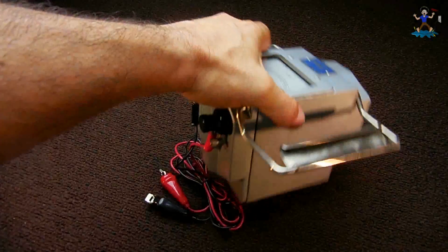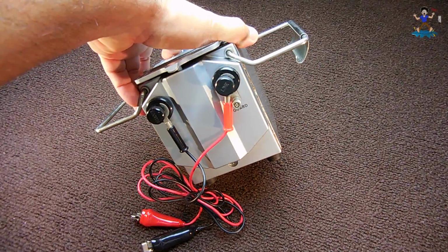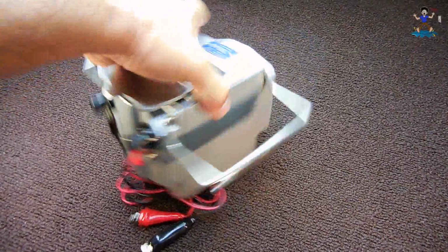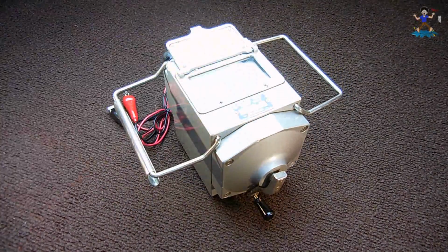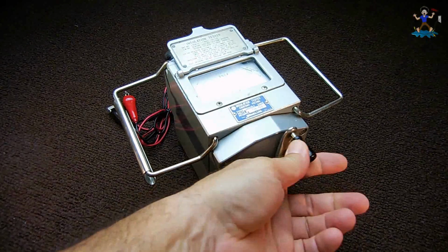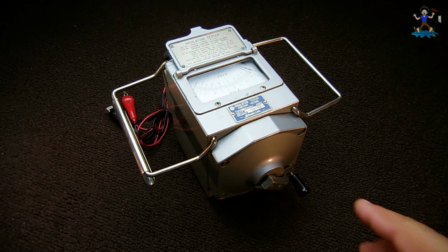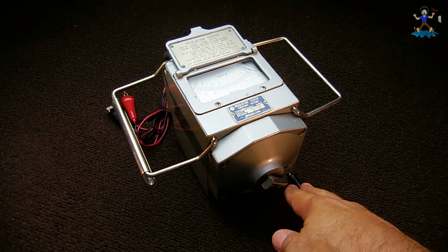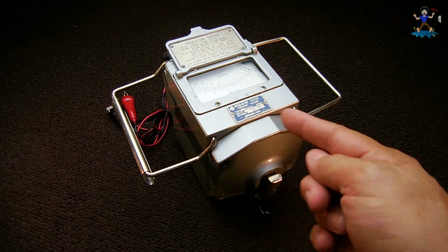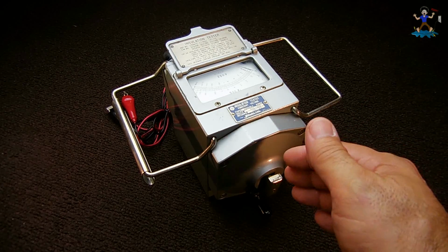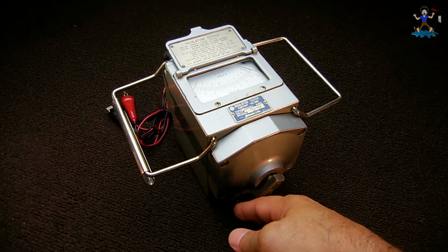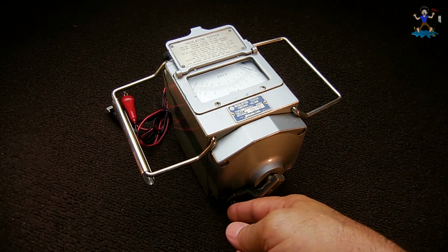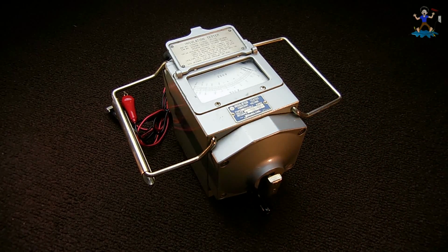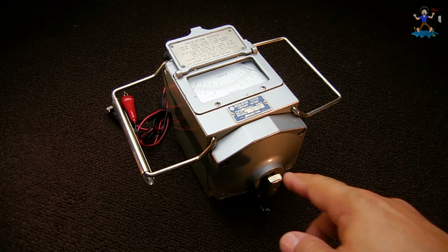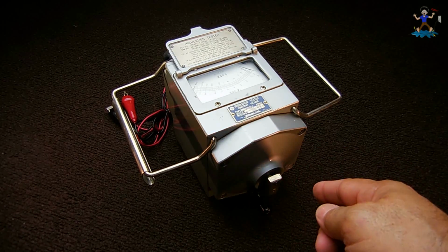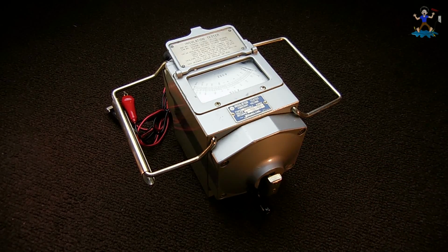On the back you have your output, positive and negative. It is a DC output that you're testing with. Over here in the front you have the crank. Now this particular unit has a built-in clutch. By design, once you start cranking it at a fast speed, you're going to feel it slip. And that slip is intentional because that's what regulates the voltage output. If this didn't start to slip and you continued to crank faster and faster, the voltage would get higher and higher. So let me just demonstrate. I'm going to spin this by hand. You're going to hear how it operates, and then you're going to hear when it starts to slip.